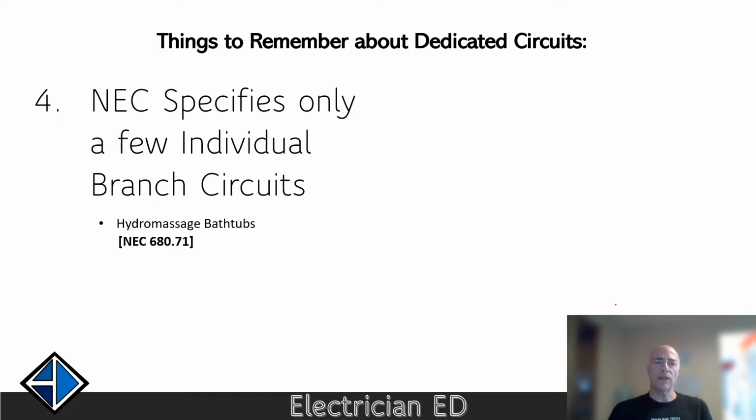And note that if the instructions depict a GFCI duplex receptacle device, that could cause some confusion. Sometimes they do depict it that way. But what you're learning now is that that would not technically be an individual branch circuit. It may be okay because it's out of the way.